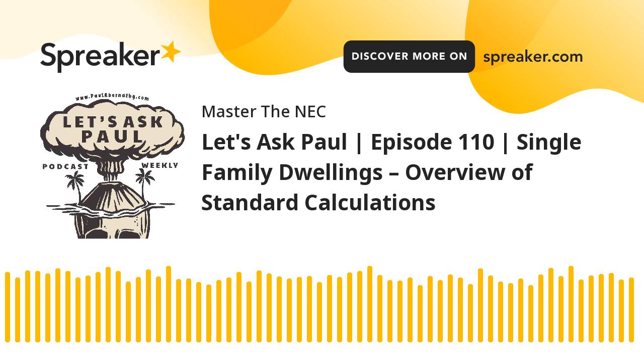Okay? All right. So assuming we're able to apply 310.12(A), we meet all these rules. Basically, it's weatherhead coming down, going through the meter, hitting a service disconnect outside that meets the requirements of 230.85. Everything's good. Is it 95 or 85? I think it's 230.85. Hold on. Having a brain fart. But that's the beautiful thing, I can go back and look. Maybe it's 85. Let's go look. Yes, it's 85. I'm sorry, 230.85. That's emergency disconnect. It's meeting all that. The option we're using is a service disconnect outside. So we're marking it as emergency disconnect and service disconnect.